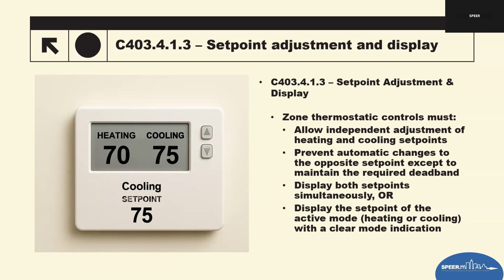That means changing one should not automatically change the other. I've seen those in the past, where as you turn one up the other one changes as well, to get closer, just using that deadband. It should be independent of each other. No automatic set point shift. So when the user adjusts the heating set point or cooling set point, it doesn't modify the opposite set point. So it cannot lock the set points together.